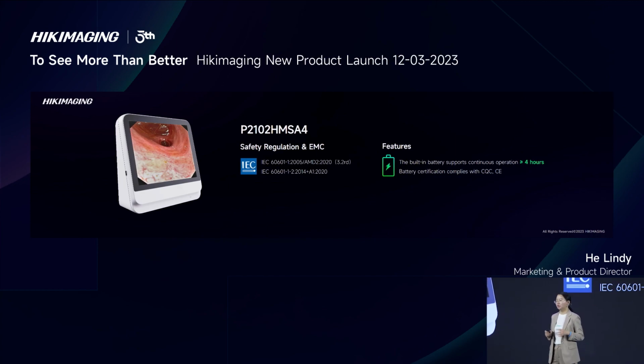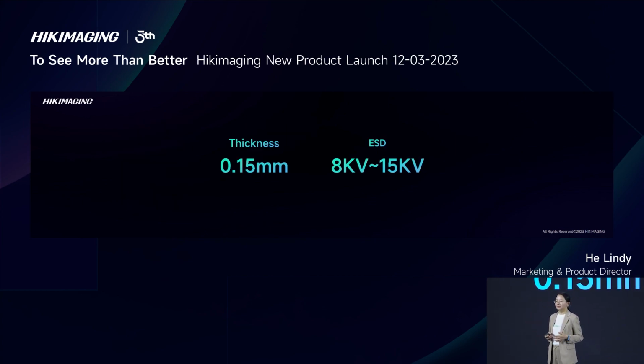And we added a solution on SA4, so it meets the safety requirements of IEC 60601-1-2005. And it also meets the EMC requirements of IEC 60601-1-2-2014. It saves a lot of work for the future CE certification. In addition, we spent more than 1 year around several numbers. One is 8 kilovolt. The other is 15 kilovolt. 8 kilovolt is for contact discharge, while 15 kilovolt is for air discharge. And both of them are requirements of ESD items.